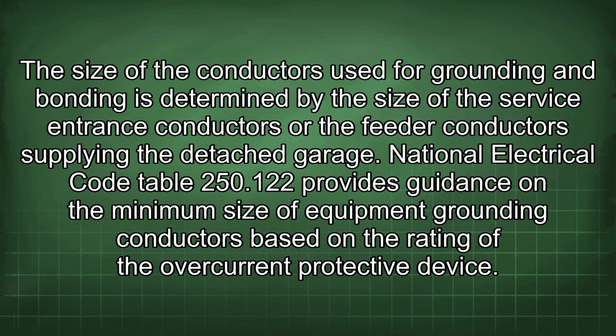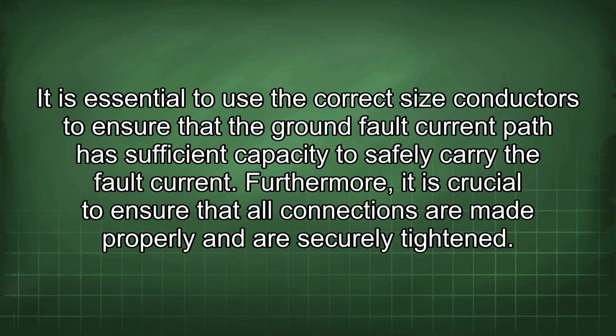The size of the conductors used for grounding and bonding is determined by the size of the service entrance conductors or the feeder conductors supplying the detached garage. National Electrical Code Table 250.122 provides guidance on the minimum size of equipment grounding conductors based on the rating of the overcurrent protective device. It is essential to use the correct size conductors to ensure that the ground fault current path has sufficient capacity to safely carry the fault current.